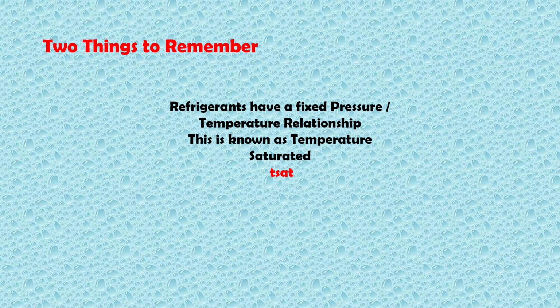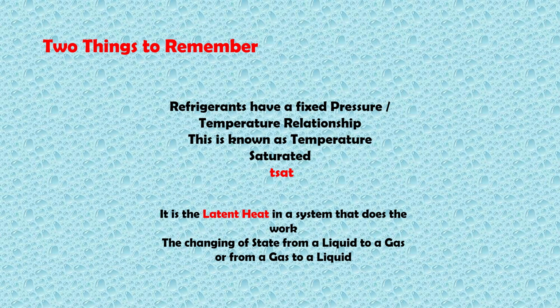Now there's two things you should really remember. Refrigerants have a fixed pressure temperature relationship - this is known as temperature saturated, or TSAT - and it's the latent heat in a system that does the work, the changing of state from a liquid to a gas, or from a gas to a liquid.